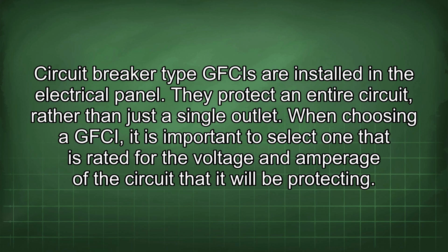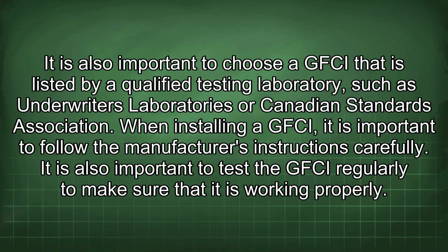When choosing a GFCI, it is important to select one that is rated for the voltage and amperage of the circuit that it will be protecting. It is also important to choose a GFCI that is listed by a qualified testing laboratory such as Underwriters Laboratories or Canadian Standards Association. When installing a GFCI, it is important to follow the manufacturer's instructions carefully. It is also important to test the GFCI regularly to make sure that it is working properly.